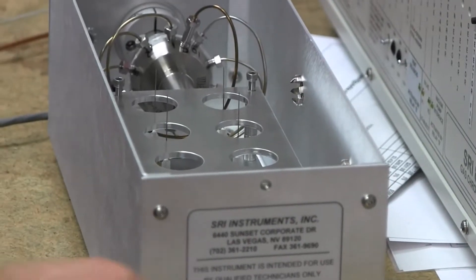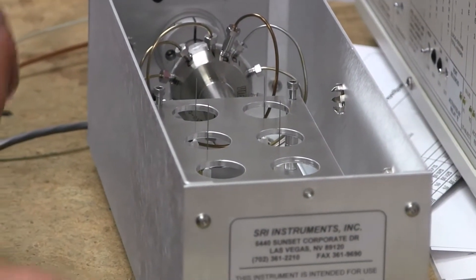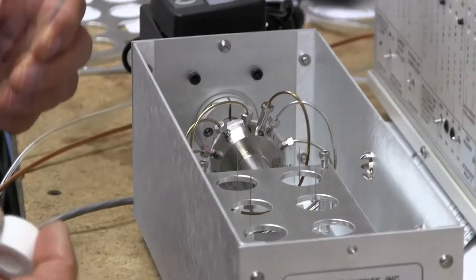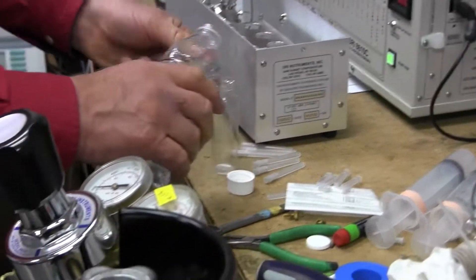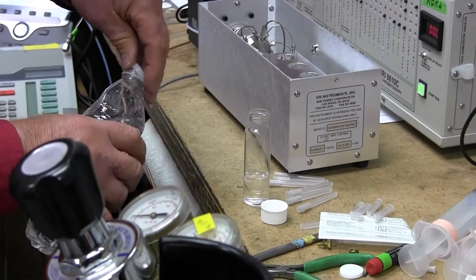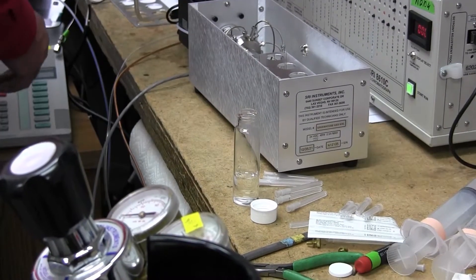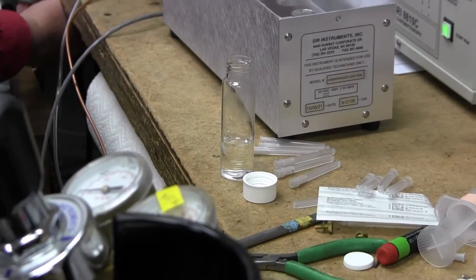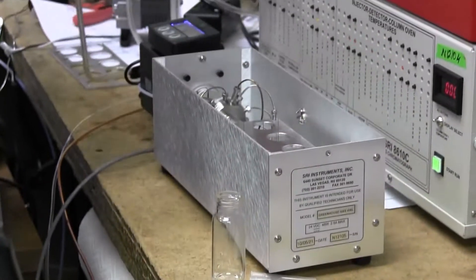Okay, so how do you know the needle is properly installed? Well, the way we do this is we use one of the vials that's going to go in the auto sampler, but we fill it with a little bit of water. So I'm going to put a little bit of water in one of these vials. Not all the way to the top, just like a quarter of the way.